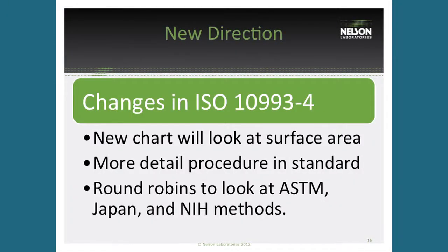This helps things like stents and other small devices that might not have to do as much hemocompatibility testing as they currently do. The other thing we're looking at in the standard is getting more detail in the test procedure itself, especially regarding hemolysis. There are currently three methods for hemolysis that labs can follow: an ASTM method, an NIH method, and a Japanese method. The question is how do those methods compare to one another.